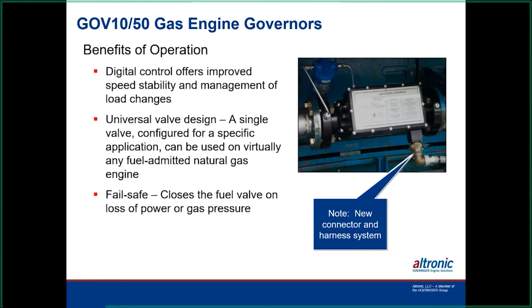Another thing we've added is a filter, if you can see it in the picture there, where we're filtering the fuel gas coming in. So if you have some dirty gas in there, it helps keep particles from getting inside the valve that is needed to control it. By changing some orifices or some plugs around, these also can be operated on shop air, as long as the shop air is 25 pounds above the supply pressure on it. So that's another way to keep the valve clean.